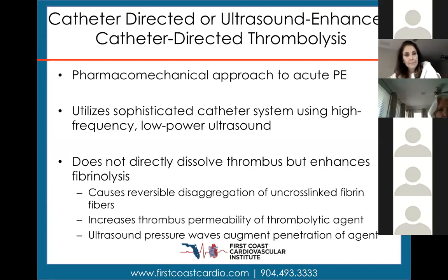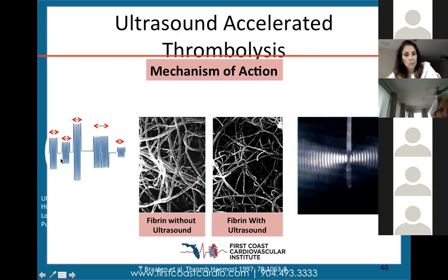And the goal is actually to break the fibrin and expose the thrombus more, increase the surface area, and increase the exposure of the thrombus to our lytic agents. So these are different waveforms that are transmitted by the device, and this is the fibrin without ultrasound, and these are the fibrin complexes with ultrasound. You see it breaks them down and increases the surface area to the lytic agents.